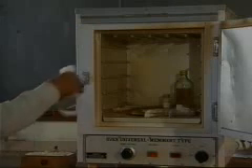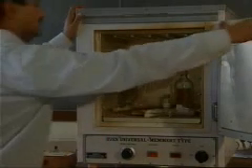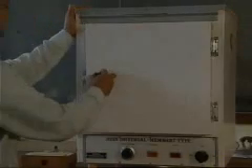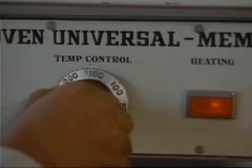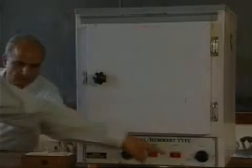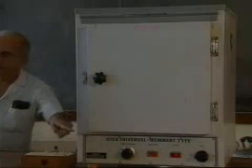After packing, the objects are kept inside the chamber, taking precautions that they do not touch the walls. The door is closed, the temperature is adjusted to 160 degrees centigrade, and the switch is put on. The current is switched off after 1 to 2 hours as required. When the chamber is cool, the door can be opened and the sterilized objects are ready for use.